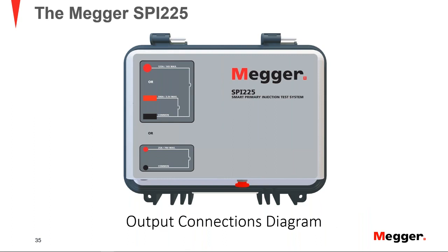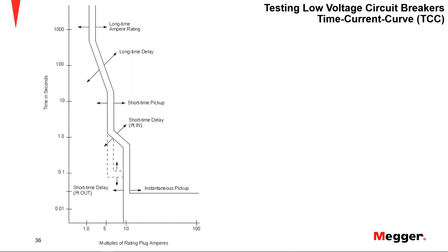What are we going to measure? And for that, we can look at the well-known time current curve. And again, for us to have a level ground and understand what we're measuring, let's review a little bit of what this curve is describing. It will actually tell me the performance of the breaker that I'm testing.